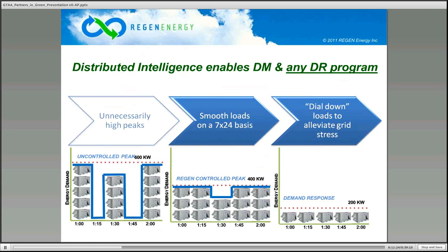So how does demand management work? If you look at the left-hand graph, you can see an uncontrolled system. At 1 o'clock all the units come on and finish their cycle. At 1:15 they're all off. At 1:30 a bunch of them are back on, then 1:45 they're off, and at 2 o'clock they're back on again. Those 5 units that come on set the peak for that day or that month. It only has to happen in Ontario usually for 15 minutes once a month, and that sets your peak. So anything you can do to keep that down is good.